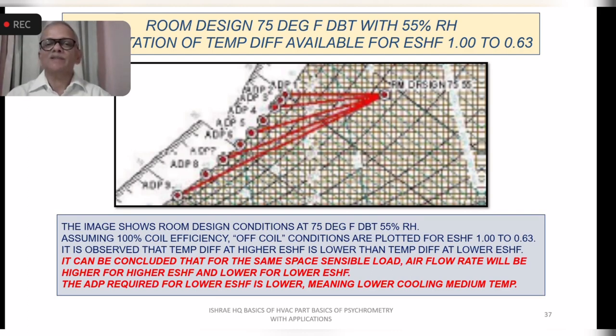Whereas if you have the sensible heat ratio lower, which means the component of the latent heat is more, then you get a higher delta T available for the sensible heat pickup. And then the amount of air to be recirculated or supplied to the space will be lower. So that is the effect of the sensible heat factor on the air quantity.